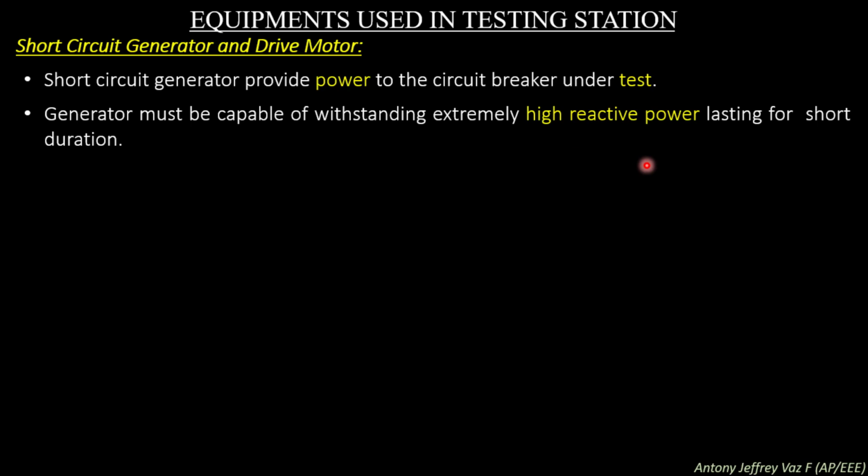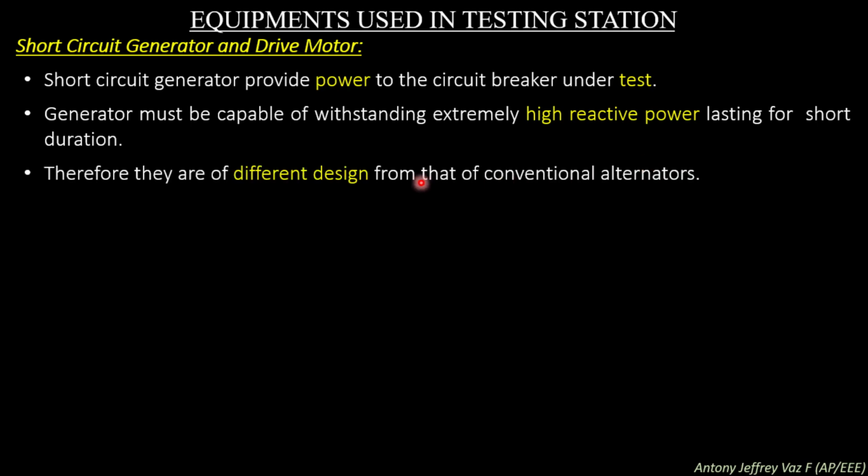So, a short circuit generator with a drive motor is arranged in the laboratory so that it will be helpful for providing the short circuit current for the circuit breaker under test. This generator has a very high reactive power withstanding capacity and gives us a very high short circuit current. Therefore, they are of different design from the conventional alternators.